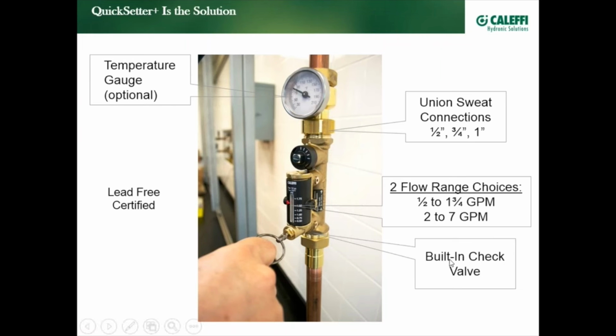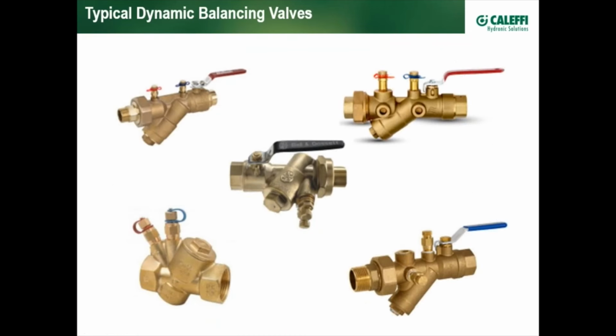Built-in check valve, prevent any thermal siphoning, and then a choice of either 0.5 to 1 3/4 gallons per minute, such as the scale used on this valve, and 2 to 7 gallons per minute. Dynamic balancing valves, great brands on the marketplace.